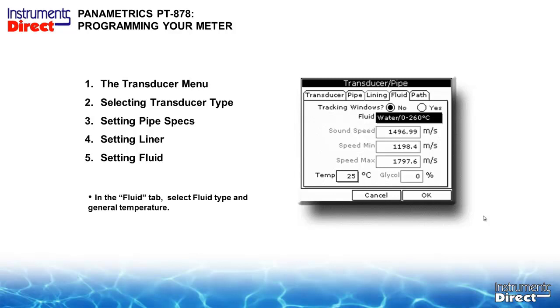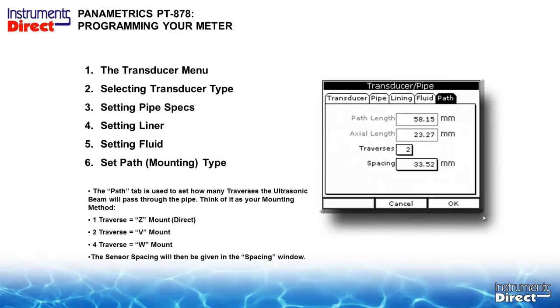In the case where you have your HVAC application, we have water and glycol. You can see the bottom lower right hand corner. You can actually plug in your 30% glycol, which is traditional. But as I said, the generic rule is plus or minus 10% of the sound speed. It doesn't make a whole lot of difference. If you look at the difference in sound speed of water and 30% glycol at nominal temperatures, you're not going to be outside that 10%. So in a lot of cases, you can just leave the meter set up on water and get correct data.